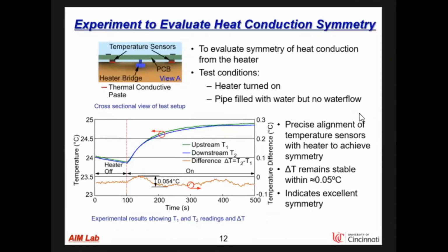The symmetry of heat conduction from heater is important to minimize sensor offset. This was experimentally evaluated with the assembled device mounted on a copper pipe as shown here. The heater was turned on with the pipe filled with water but no water flow. The readings from both temperature sensors are plotted here. Both T1 and T2 readings show a consistent 1 degree increase after the heater was turned on. The delta T shown in brown color remained stable within a small range of 0.05 degrees Celsius, indicating excellent symmetry of heat conduction achieved by the symmetric design of the device structure and thermal isolation.